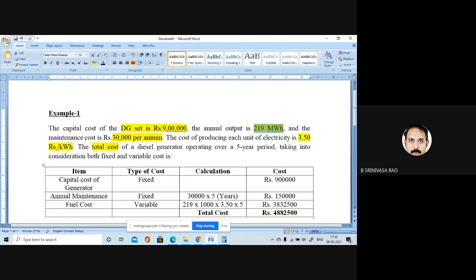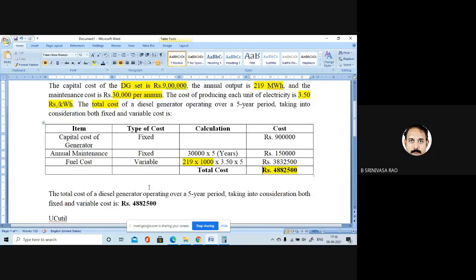The annual output is 219 megawatt hours. Since the rate is in kilowatt hours, I have converted 219 megawatt hours into 219 × 1,000 kilowatt hours, multiplied by 3.5 rupees per kilowatt hour, multiplied by five years — coming to 38,32,500. So the total cost, if you are going to operate this particular diesel generator for five years, is 48,82,500. The fixed cost — 9 lakhs plus 1,50,000 — is around 20 to 21 percent of the total cost.